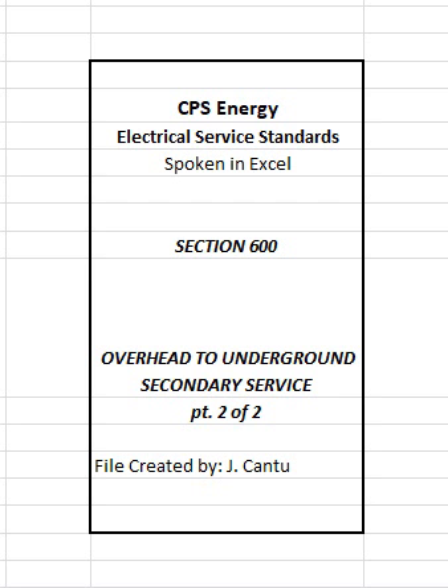5. Trench for conduit sleeves shall be backfilled with approved materials in accordance with CPS Energy specifications. Note: for other than residential driveways, trench and conduit sleeves shall be backfilled with flowable fill up to no less than 6 inches of pavement surface. 6. All sleeve routes and locations require CPS Energy approval and inspections prior to backfilling, refer to Article 604.12 and 604.13. Exception: sleeves installed under residential driveways.